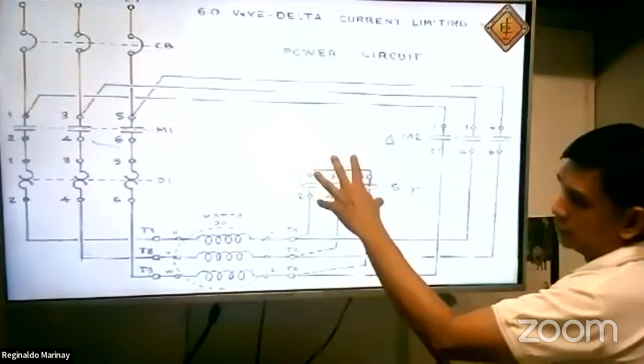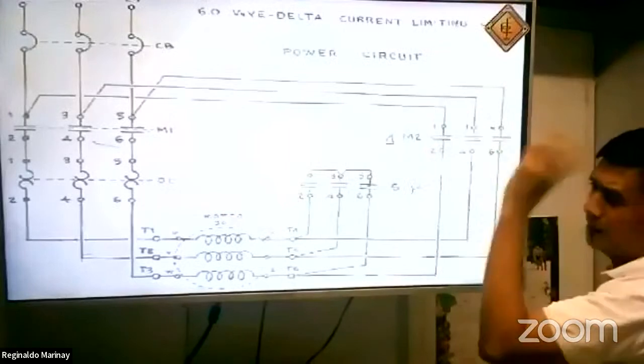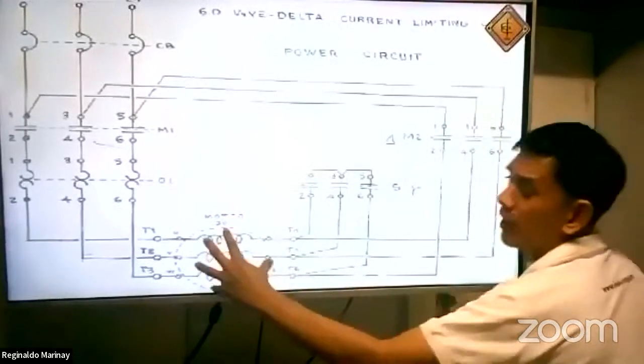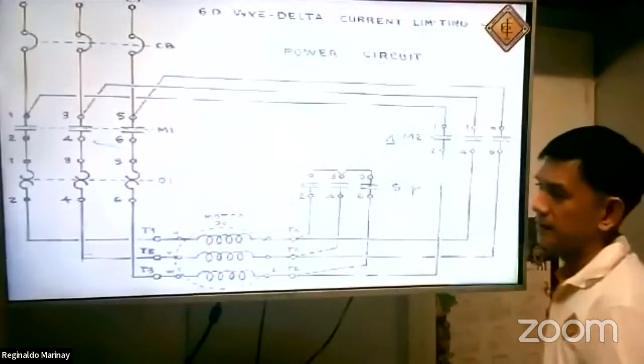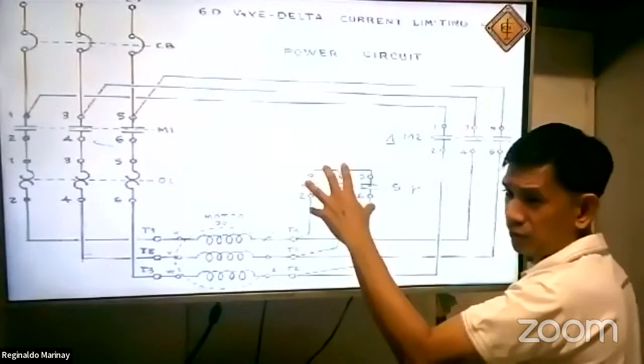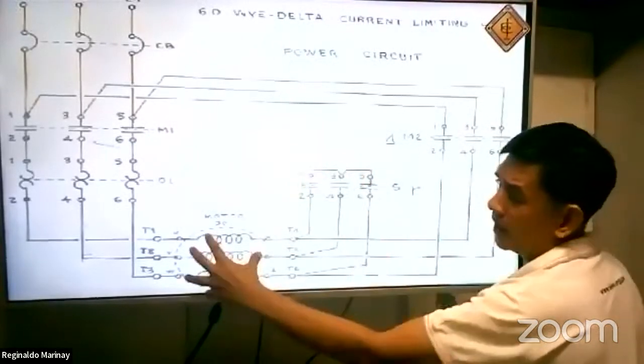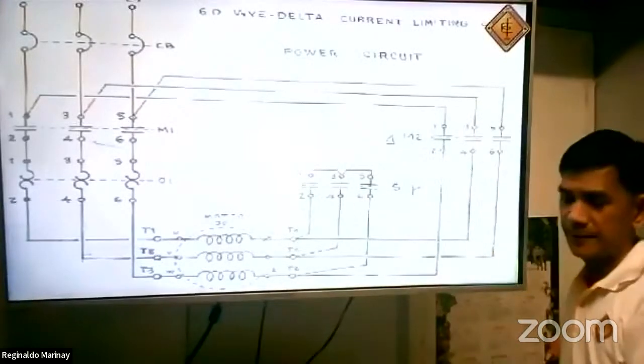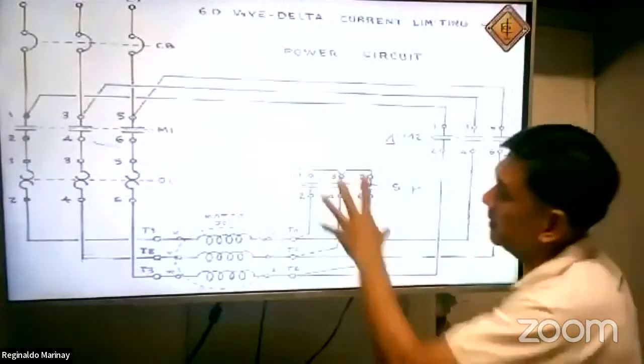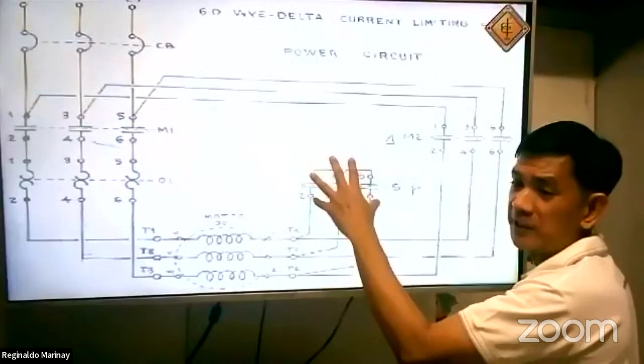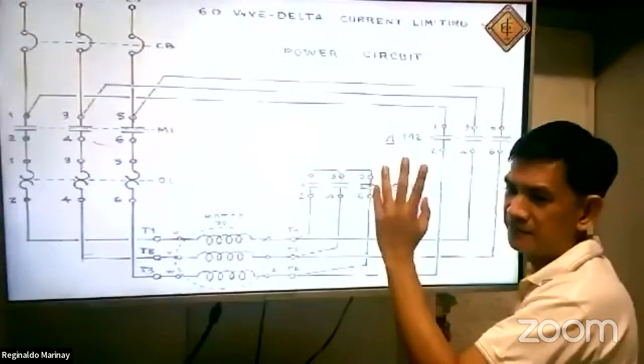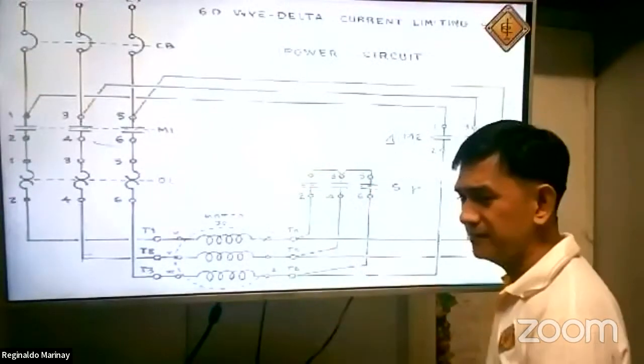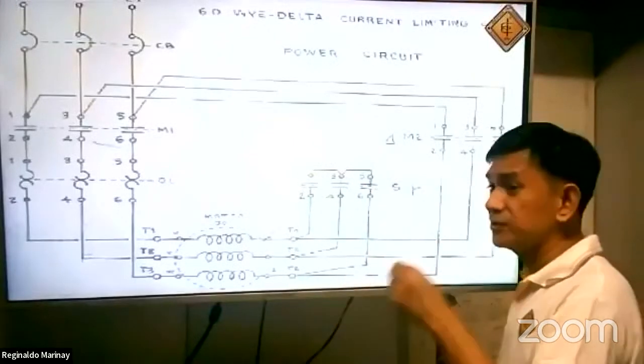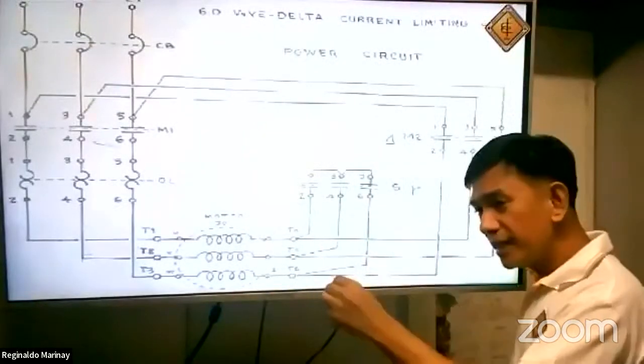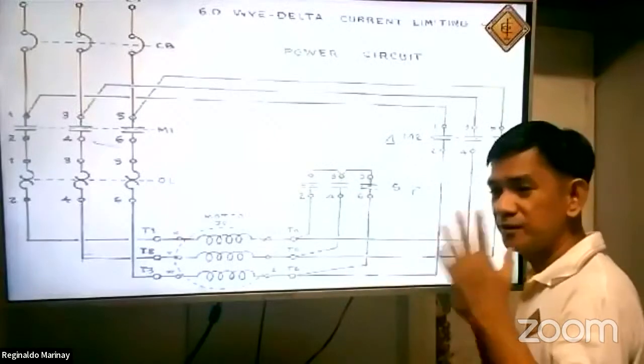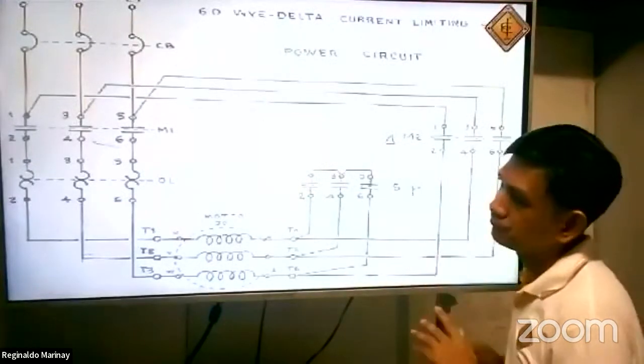We have a Y contactor and a delta contactor, meaning this contactor will make this winding delta connected. This Y contactor will make this winding Y connected. So therefore, initially, the connection is Y. That's why it is called Y delta, because Y is the starting condition of the motor. Delta is the running condition, once you reach 3 seconds onward, let's say.